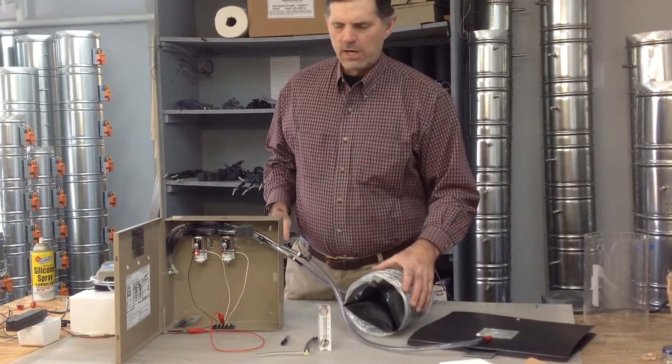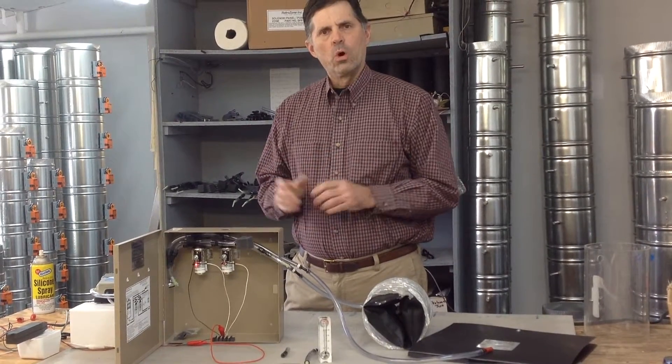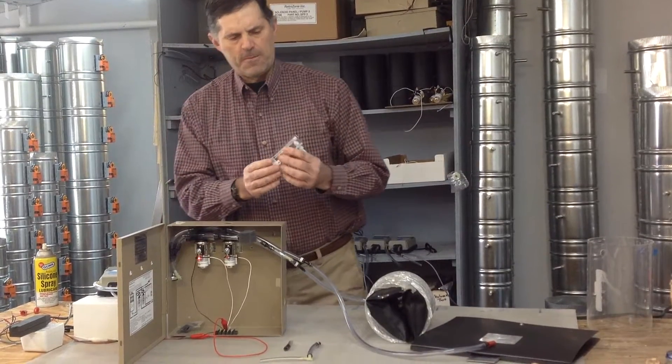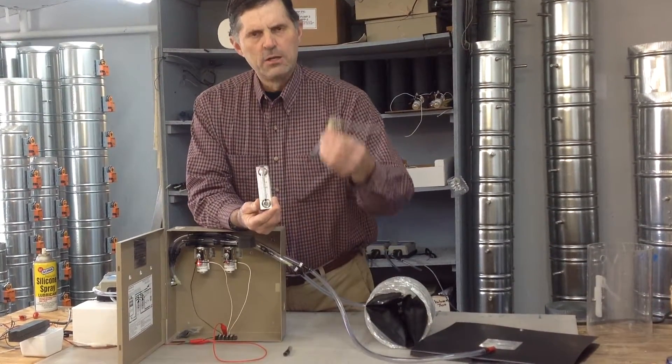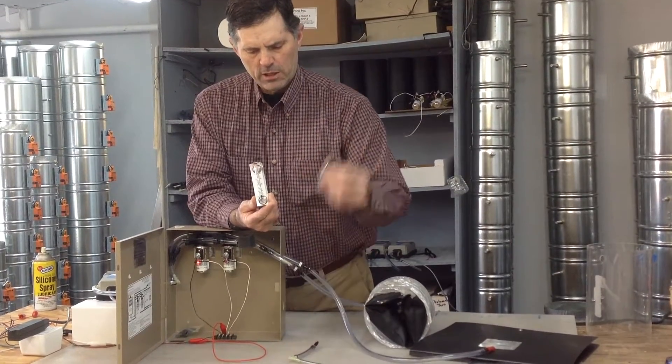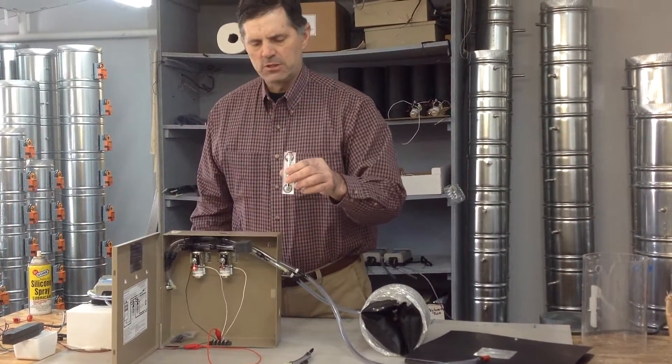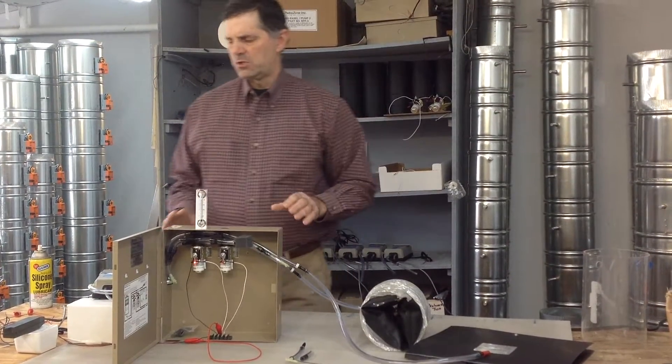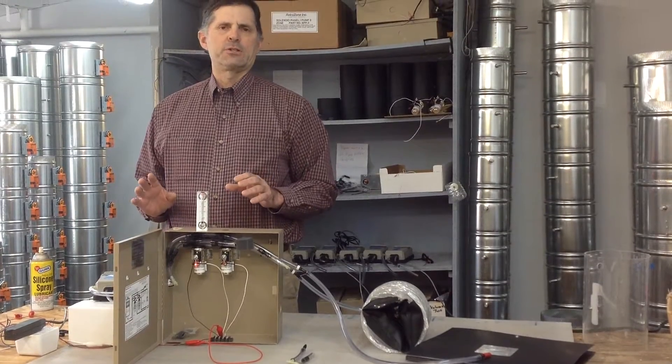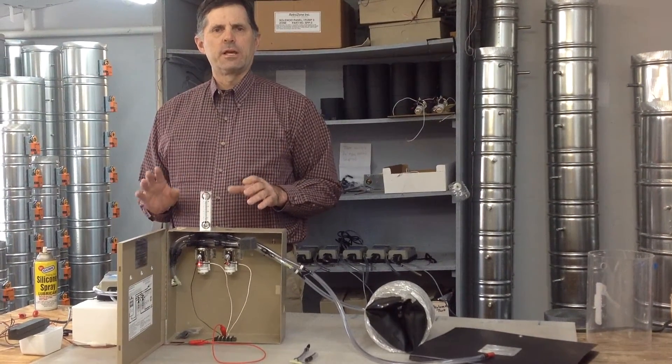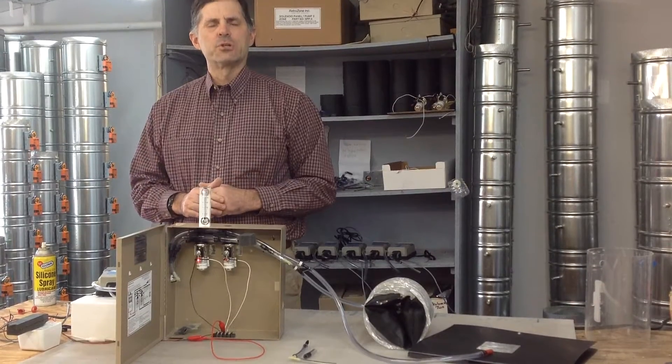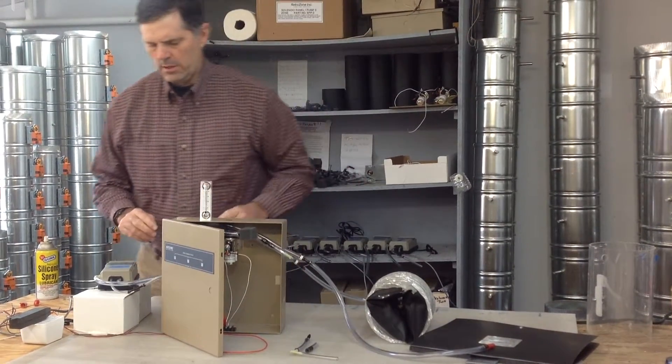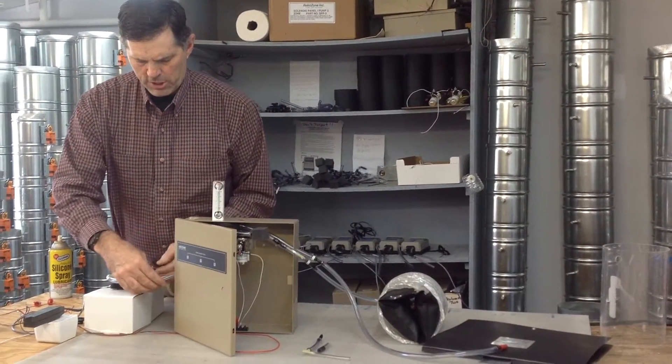Now, what happens if you've got a system, you're looking at it, you're not sure what's working and what's not working? This is where our new test kit really comes into play. The test kit, it's an airflow meter from Dwyer. It's got a few extra pieces of tubing and a plug and some parts just to make this easy to do. The most service-oriented part of this system is the pump. The pumps tend to last anywhere from 4 or 5 years to 10, 12. We have some out still going after 15 or 16 years of operation.